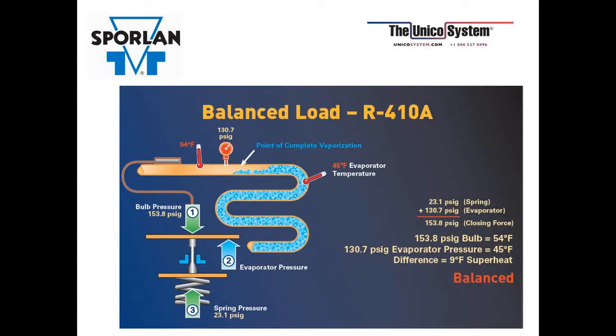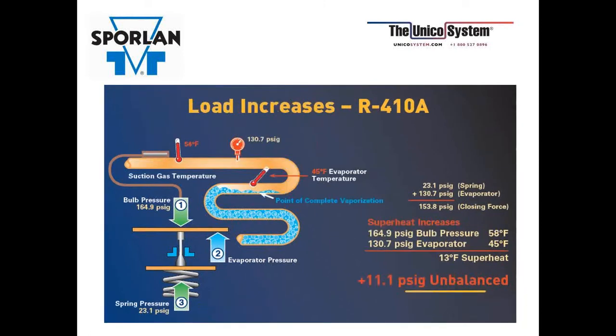You notice that point of complete vaporization, or the starve point, is right there at that last end before it heads out of the outlet of the evaporator. As the load changes in the evaporator, the pressures at points 1 and 2 are going to change, forcing the valve to either a more open position or a more closed position, depending on the conditions. As that load increases, now the starve point is backing deeper into your evaporator. So now you're going to start picking up more superheat. From the point that it turns to vapor, you're going to add superheat from that point on.